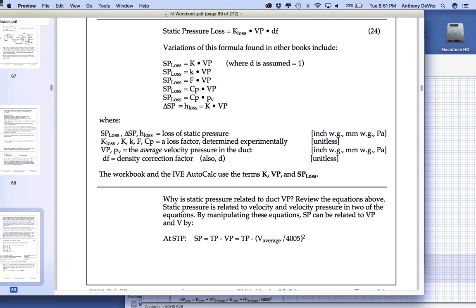Each one of these different things that are going to cause us to lose energy, we're going to have tables or calculations that have been made for us to estimate what the amount of energy loss is going to be. For ductwork, it's going to be the material of ductwork, which kind of implies the roughness. It's going to be the length of the ductwork, and it's going to be the velocity of air moving through it. For an elbow, it's going to be whether the turn is a 15-degree turn, a 35-degree turn, a 90-degree turn, 180-degree turn, right? That's going to influence how much energy we're going to use.